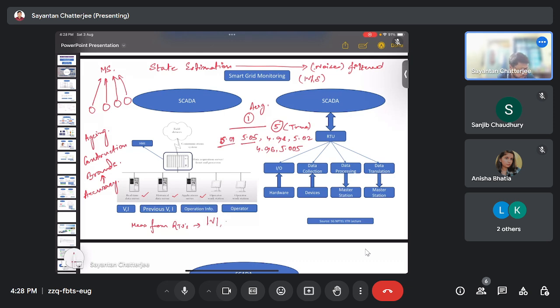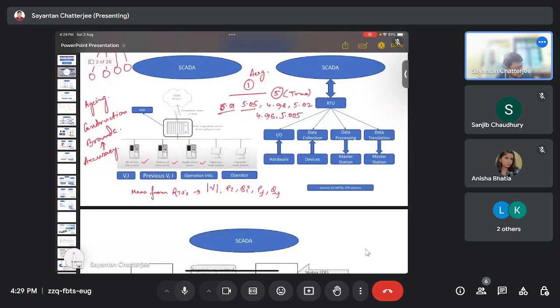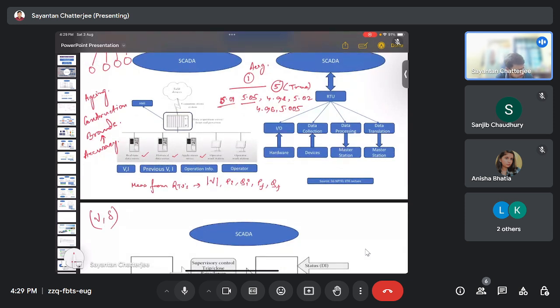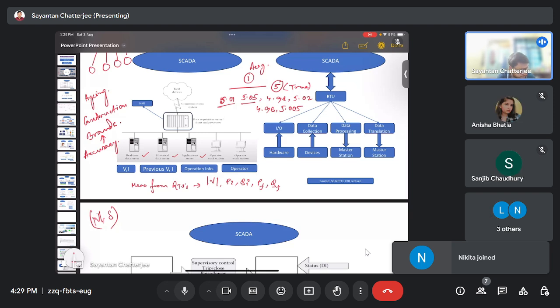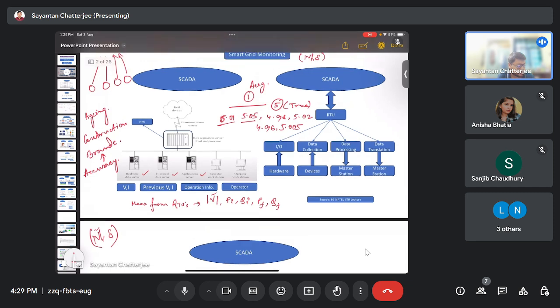Generally the measurements taken are power injections, meaning both real and reactive power injections, and power flows, real and reactive power flows. These are the measurements we obtain from the RTUs in the master station, and based on that we perform state estimation, and after that we find the results, V and delta. V is the voltage magnitude, not the voltage phasor. This information we can directly get from the RTUs, but the phase angle is absent, and to get this phase angle we need to perform estimation. That's the importance of the SCADA system.